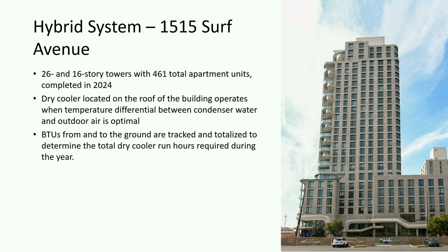So for an example of a project where we had this installed, again, another one on one of our site visits, 1515 Surf in Coney Island. For this project, we installed a dry cooler on the roof, and we have our BMS system with all of our BTU monitoring. We will track the total number of BTUs that go into the ground and the total number that come out, and we have a system that will run and totalize the hours and totalize the BTUs over the course of the year. So in a number of years, as our condenser water temperatures rise, this system will kick on, and that will stop our annual thermal drift.